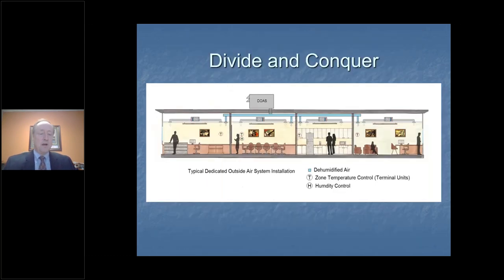I'm a big proponent of divide and conquer when I'm using dedicated outdoor air systems. I know, just like from the two charts I just showed you, when we bring in outside air, we bring in a lot of moisture in many climates. We do here in the southeastern part of the United States, and you certainly do there in your part of India. So if I know that my loads inside of my building, my moisture load as well as my sensible load or my dry bulb load, stay pretty much the same, we have the same number of lights on, the same number of computers, the same number of copy machines. So that's pretty constant throughout the day.